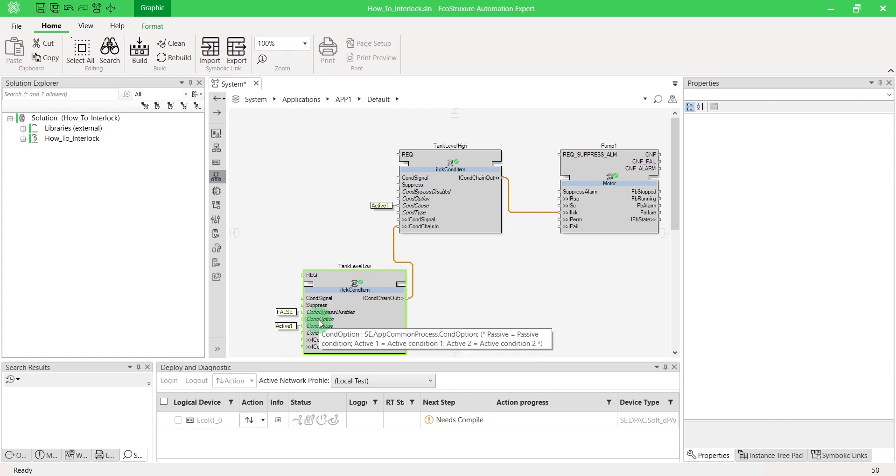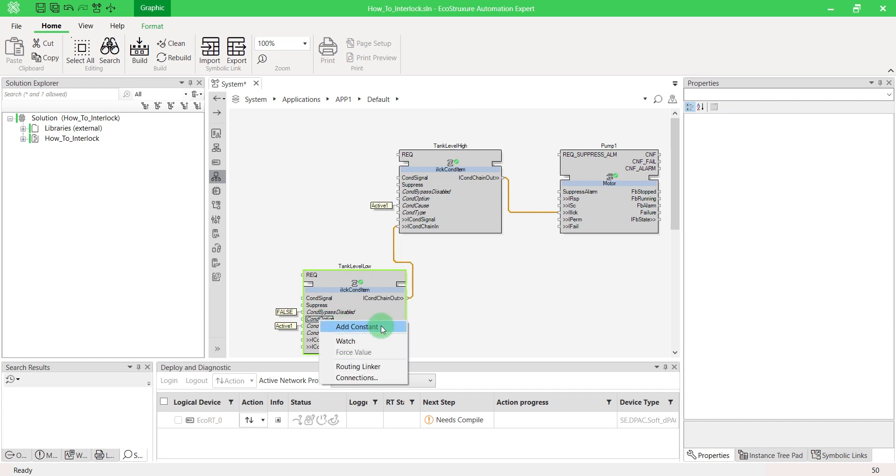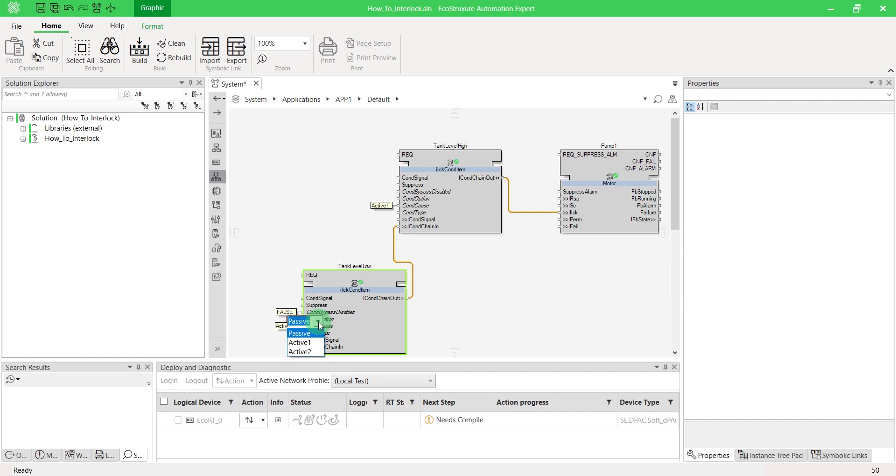Cond options defines the position of the device whenever the condition is activated, considering the bypass and suppress status of that condition. If you want to turn off your motor, then set the option as passive. Active one allows you to turn the motor on in forward mode, while active two configures the motor in reverse mode.